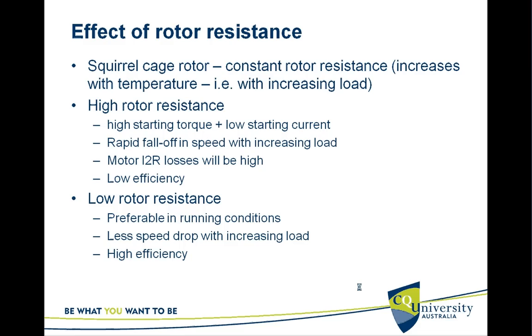When the rotor resistance is high, the starting torque will be high and the starting current will be low. But the speed will rapidly fall off with increasing load, and the I²R losses will be high because of the high rotor resistance.